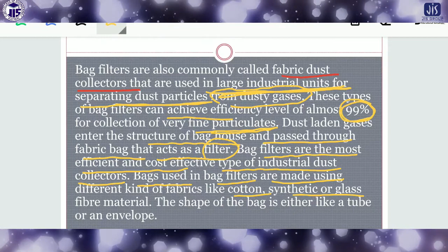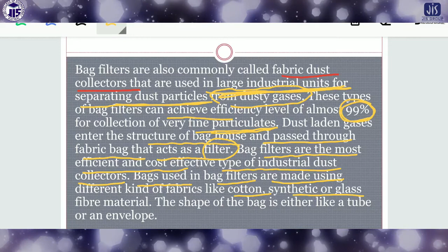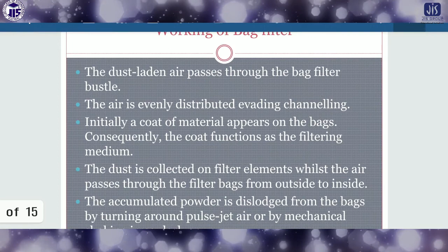Normally the dust particles are separated from the dusty gases by some filtering system, and materials like cotton, synthetic or glass fiber are generally used in the bag filter. Now, the working of the bag filter; this is the working principle. First of all, the dust laden air passes through the bag filter bustle. The air is evenly distributed, avoiding channeling.